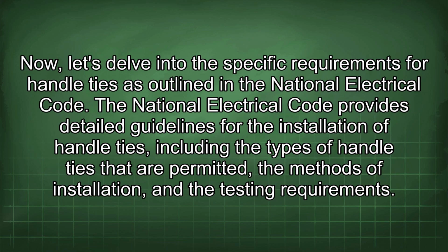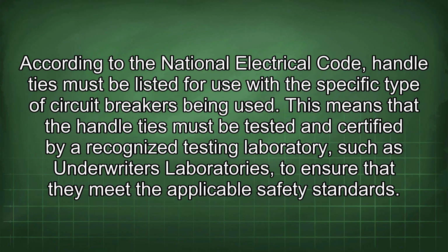Now let's delve into the specific requirements for handle ties as outlined in the National Electrical Code. The National Electrical Code provides detailed guidelines for the installation of handle ties, including the types of handle ties that are permitted, the methods of installation, and the testing requirements. According to the National Electrical Code, handle ties must be listed for use with the specific type of circuit breakers being used. This means that the handle ties must be tested and certified by a recognized testing laboratory, such as Underwriters Laboratories, to ensure that they meet the applicable safety standards.